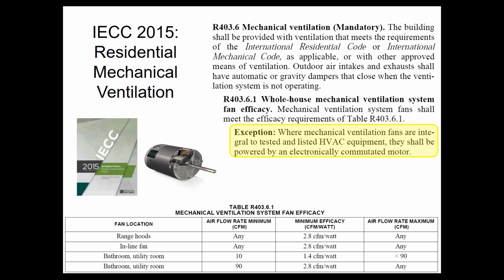If you're going to run an outside air duct to the return of your furnace and use your furnace fan to distribute the ventilation air around the building, your furnace fan has now become the mechanical ventilation fan. So it would therefore need an ECM motor. So if you're going to comply with mechanical ventilation by using your furnace, you need to have an ECM, not a PSC blower.